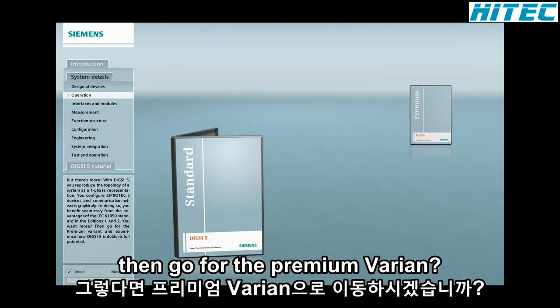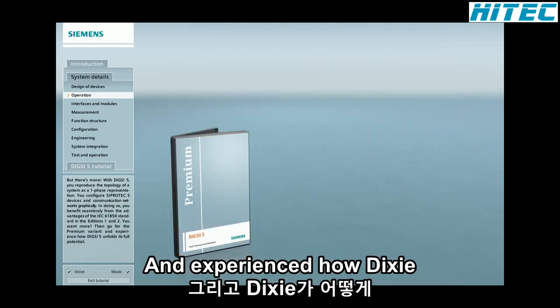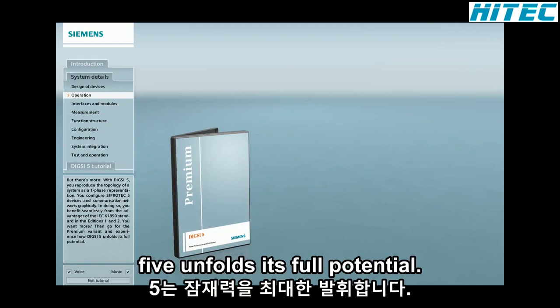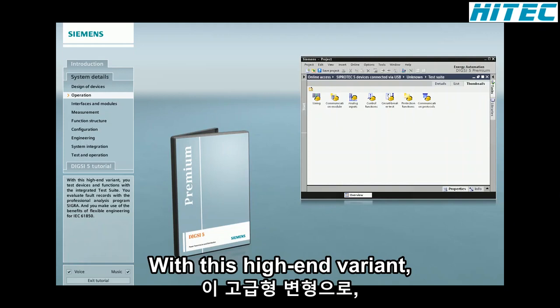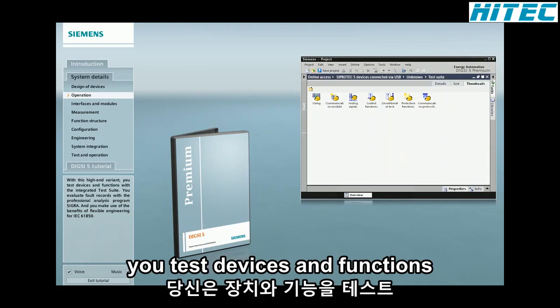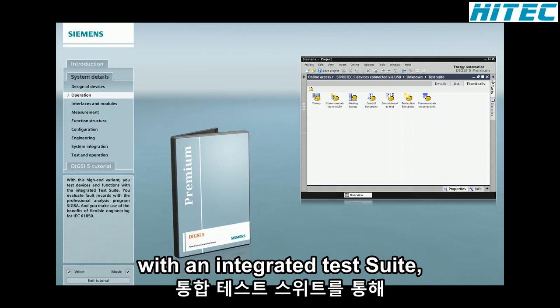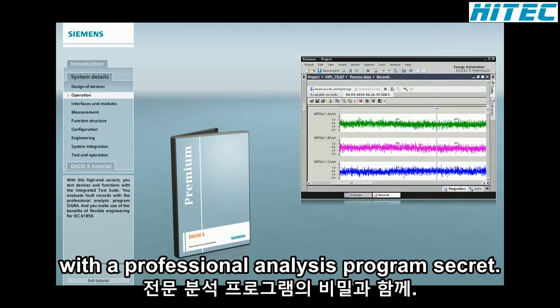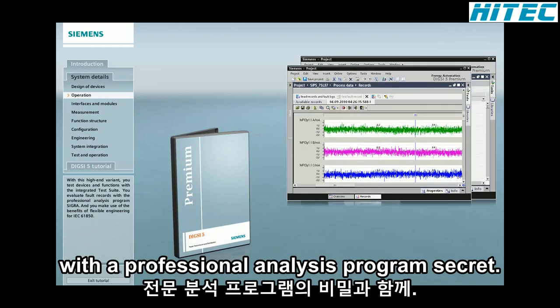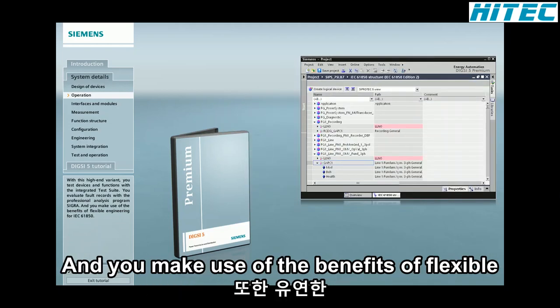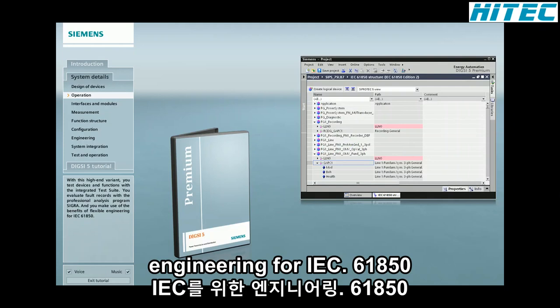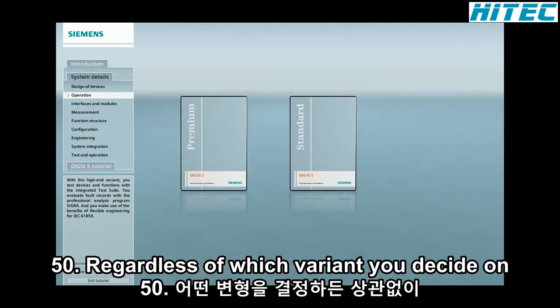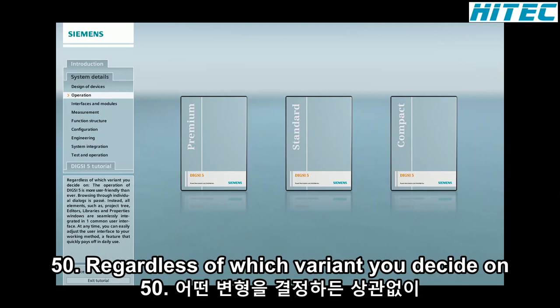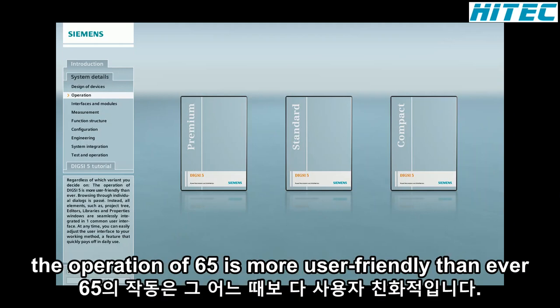You want more? Then go for the premium variant and experience how DIGSI 5 unfolds its full potential. With this high-end variant, you test devices and functions with the integrated test suite. You evaluate fault records with a professional analysis program, SIGRA. And you make use of the benefits of flexible engineering for IEC 61850. Regardless of which variant you decide on, the operation of DIGSI 5 is more user-friendly than ever.